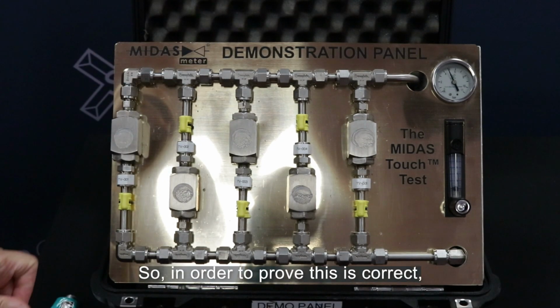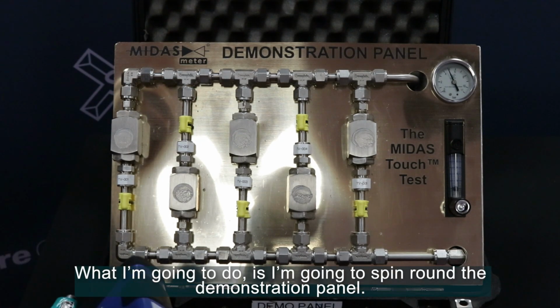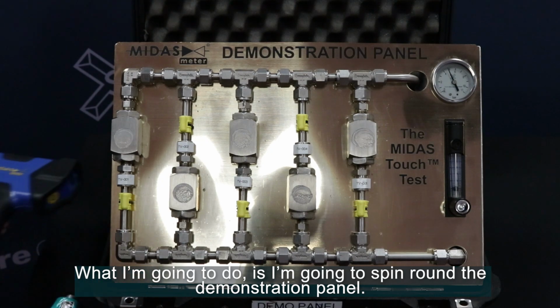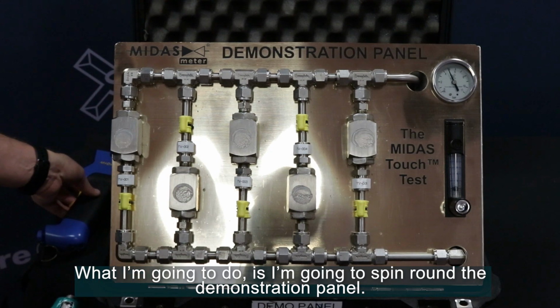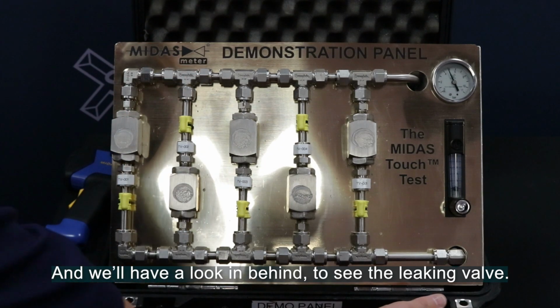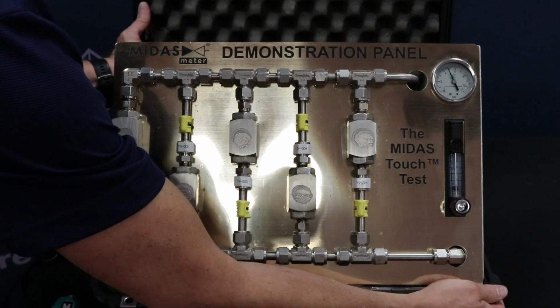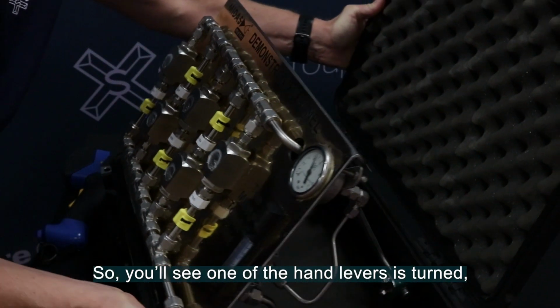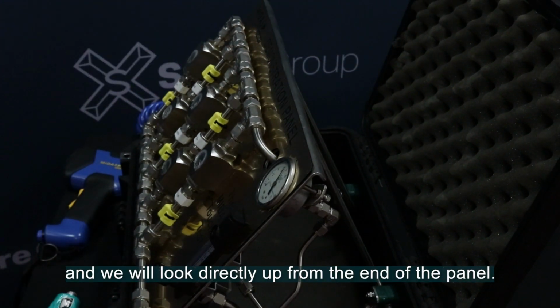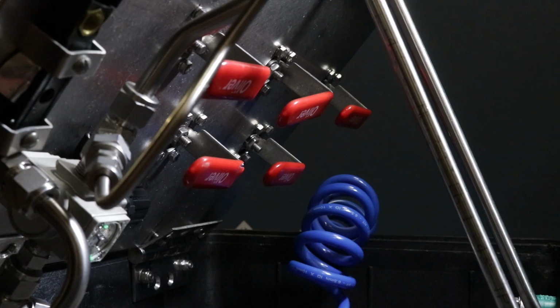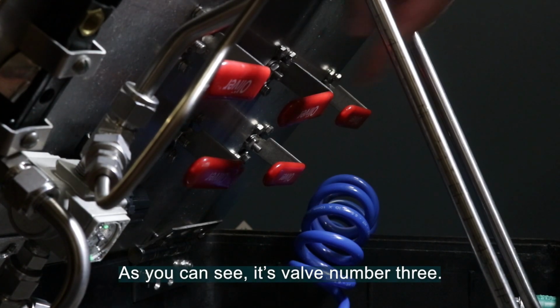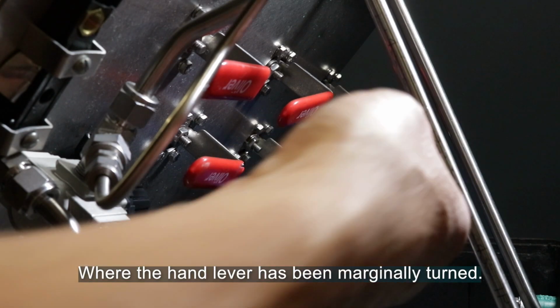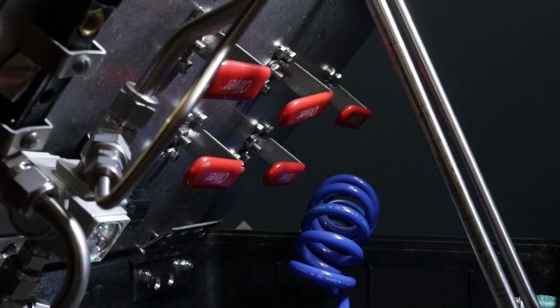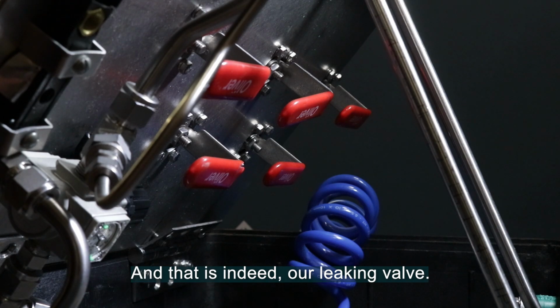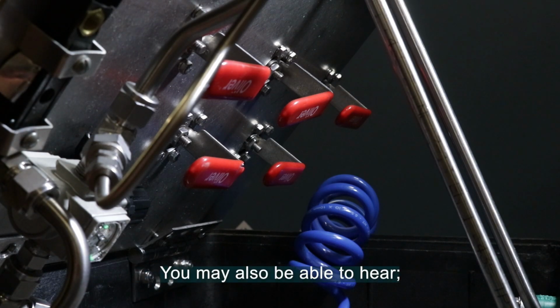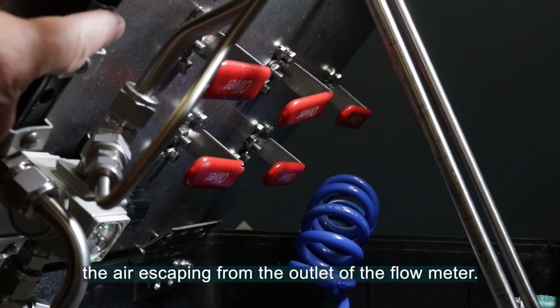So in order to prove this is correct, what I'm going to do is spin round the demonstration panel and we'll have a look in behind to see the leaking valve. So you'll see one of the hand levers is turned and we'll look directly up the end of the panel. As you can see, it's valve number 3 where the hand lever has been marginally turned, and that is indeed a leaking valve. You may also be able to hear the air escaping from the outlet of the flow meter.